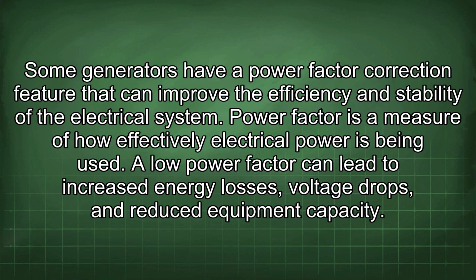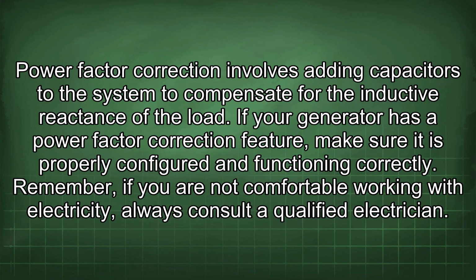Some generators have a power factor correction feature that can improve the efficiency and stability of the electrical system. Power factor is a measure of how effectively electrical power is being used. A low power factor can lead to increased energy losses, voltage drops, and reduced equipment capacity. Power factor correction involves adding capacitors to the system to compensate for the inductive reactance of the load. If your generator has a power factor correction feature, make sure it is properly configured and functioning correctly.